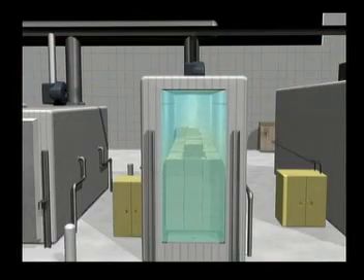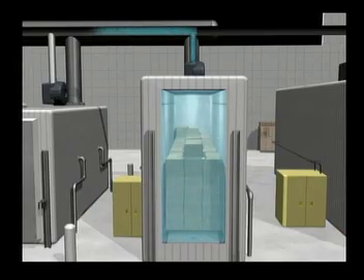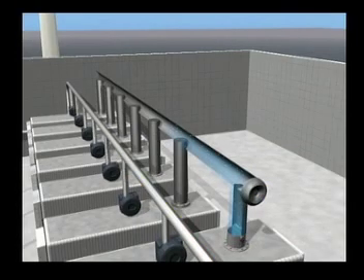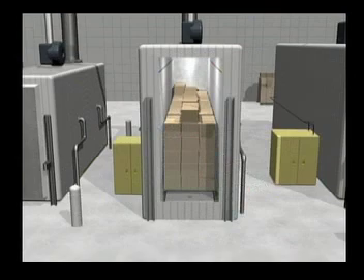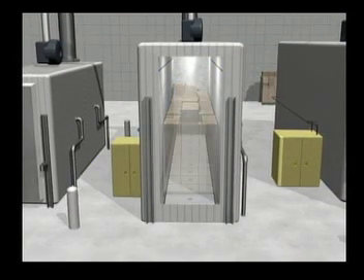The system automatically performed the normal series of gas washes, which removed virtually all of the ethylene oxide. Finally, the chamber was ventilated to the oxidizer. Operators then removed the products from the chamber.